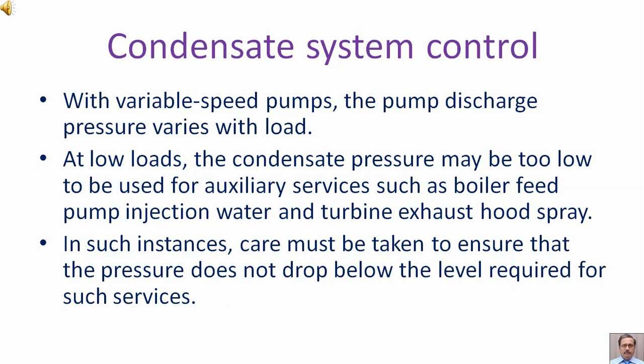With variable speed pumps, the pump discharge pressure varies with load. At low loads, the condensate pressure may be too low to be used for auxiliary services such as boiler feed pump injection water and turbine exhaust hood spray. In such instances, care must be taken to ensure that the pressure does not drop below the level required for such services.